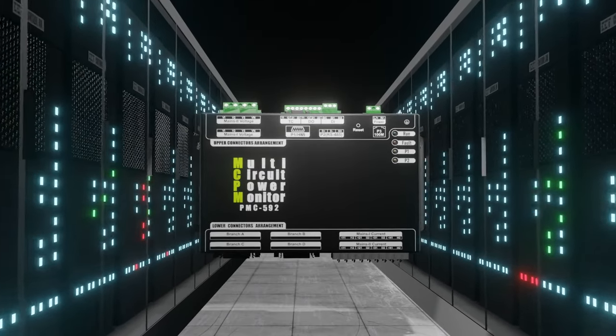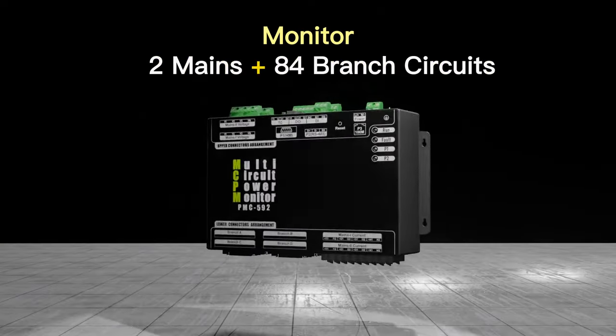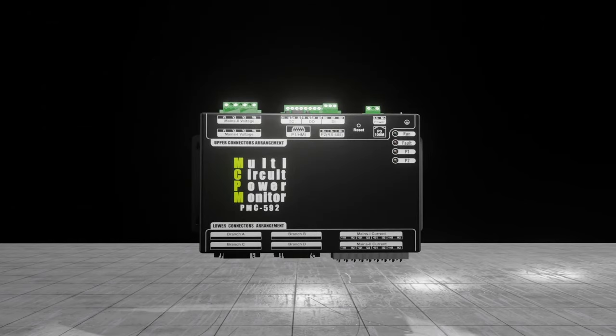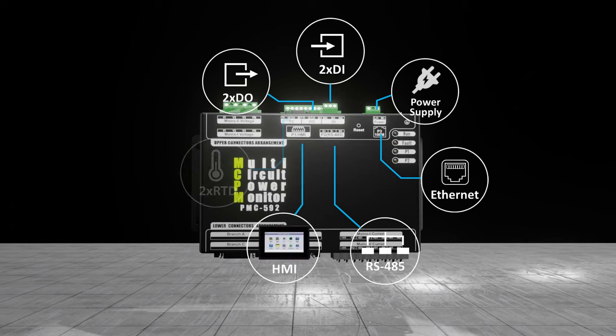The PMC592 is a multi-circuit monitor which can monitor two main circuits and up to 84 branch circuits. It provides digital I/O for status monitoring, control, alarming, as well as temperature monitoring. These signals can be easily integrated into BAS for building automation via the RS-485 or Ethernet port.